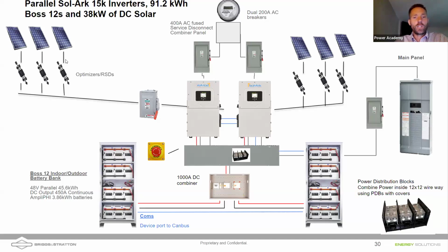What those do is there's a keep alive signal that gets sent from the rapid shutdown transmitter that keeps these devices closed unless that keep alive signal disappears. So if a fireman comes to site and hits the rapid shutdown button, that would trigger the keep alive signal to die, and then these would all open, which shuts all the solar panels down at the panel level to keep it safe. A lot of solar strings are 400 or 500 volt strings, with just vinyl over the conductors there, and that could melt in the case of a fire and could be very dangerous. And so code requires rapid shutdowns on rooftop mounted arrays.